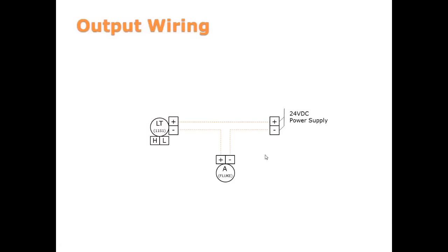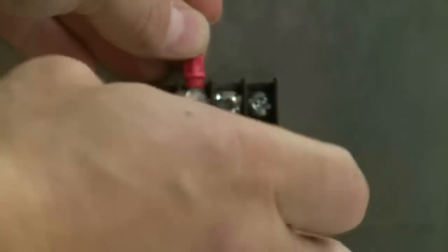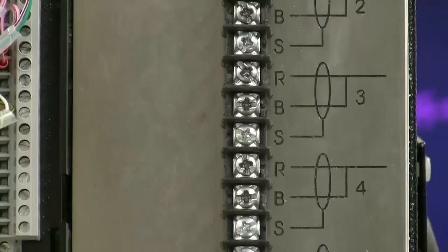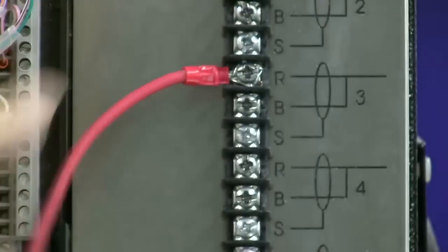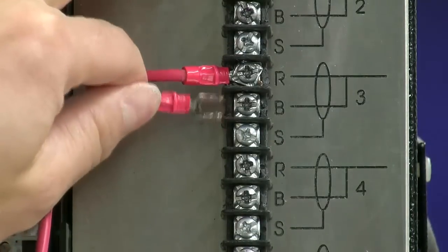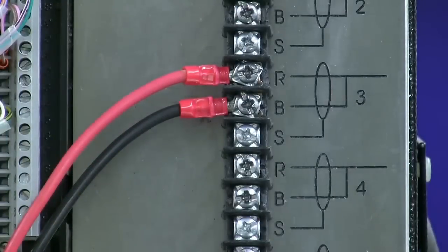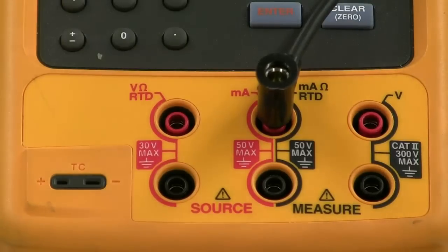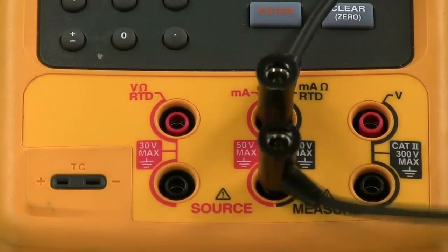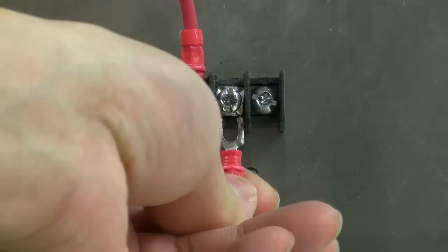We can now proceed to wire the 24-volt power supply and the Fluke to the loop. Start by connecting to the positive on the power supply. The current will flow from the power supply positive out to the transmitter positive, which is the red on cable pair 3. Coming out of the transmitter on black, it will flow into the milliamp port on the Fluke. Coming out of the common port on the Fluke, it will complete the loop at the negative of the power supply. The completed loop should look something like this.